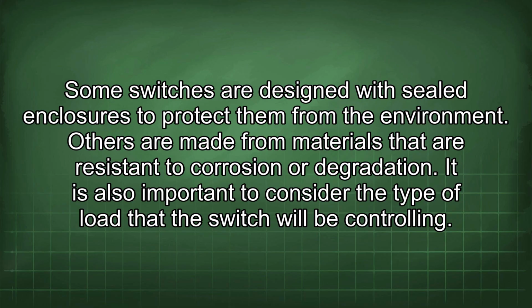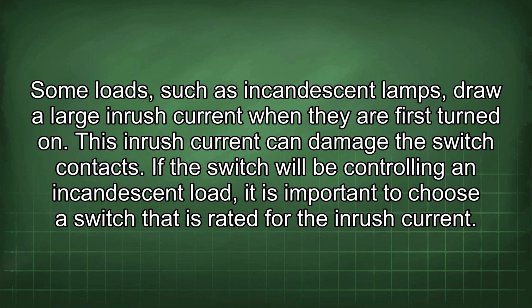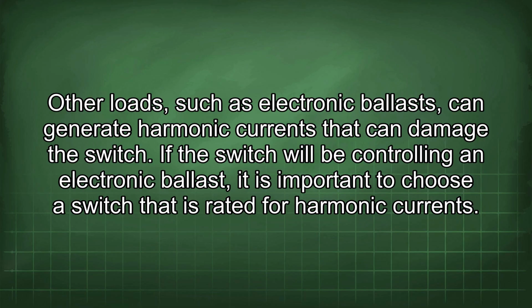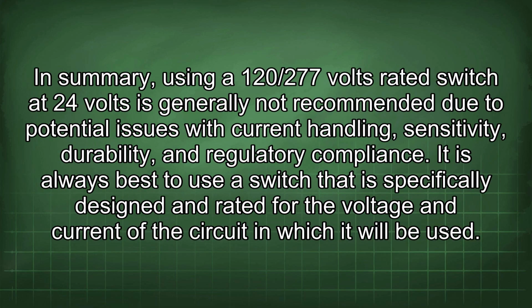It is also important to consider the type of load that the switch will be controlling. Some loads, such as incandescent lamps, draw a large inrush current when they are first turned on. This inrush current can damage the switch contacts. If the switch will be controlling an incandescent load, it is important to choose a switch that is rated for the inrush current. Other loads, such as electronic ballast, can generate harmonic currents that can damage the switch. If the switch will be controlling an electronic ballast, it is important to choose a switch that is rated for harmonic current.